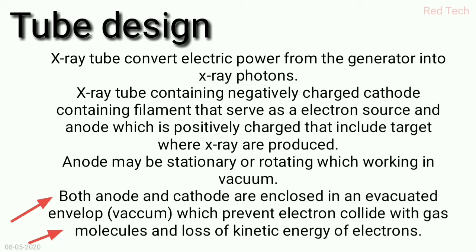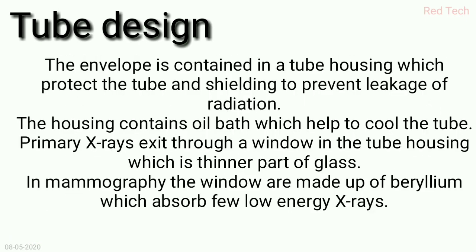Both the anode and cathode are enclosed in an evacuated envelope — basically in vacuum with no air present. This prevents electrons from colliding with gas molecules and losing kinetic energy. If air were present, the energetic electrons accelerating towards the anode might lose their kinetic energy.